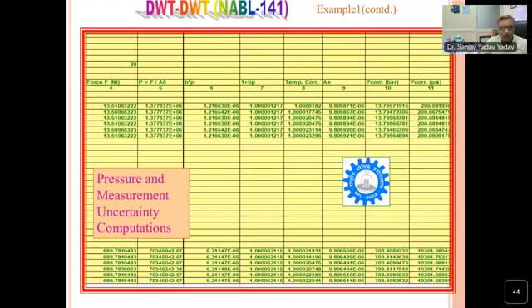And for the numerator, first you have to determine the nominal value. Because if you see the equation, A naught multiplied by 1 plus BP. So here itself P is coming, and on the left hand side of the equation P is coming. So this P is basically the nominal value. Normally people make a mistake here because they do not understand what this 1 plus BP is. So this P is the pressure value before correction, meaning it is the force divided by A naught only. Then we have to determine 1 plus BP. This is normally around unity. If the temperature is more, it will come in plus. If the temperature is less, it will come as 0.999.